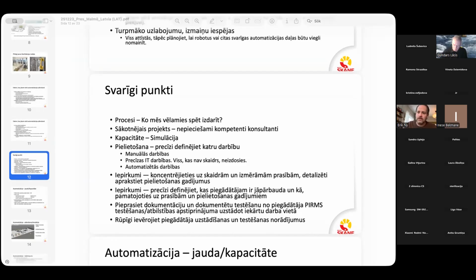You need to be very strict with those things, because my experience is otherwise the suppliers kind of take the chance that things are working and that the site acceptance test will be approved, but it's not necessarily the case. If you plan a site acceptance test and you then want to start using your equipment, and the supplier cannot meet your requirements and you only find out at the site acceptance test, you will probably have big problems with your time plan after that. And since we are serving the surgical wards, it's probably pretty devastating.